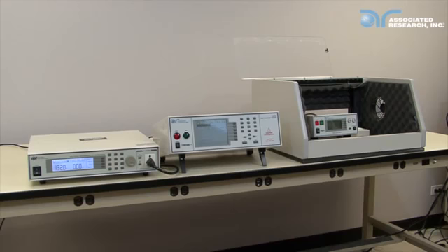Next, we're going to show you how to connect an external power source to the 620L. This will allow you to run power through the 620L to power up the DUT during the line leakage testing. Then we'll connect the 620L to the DUT and run a test sequence.